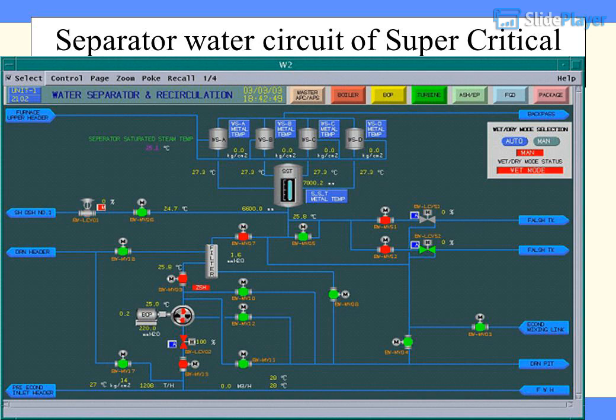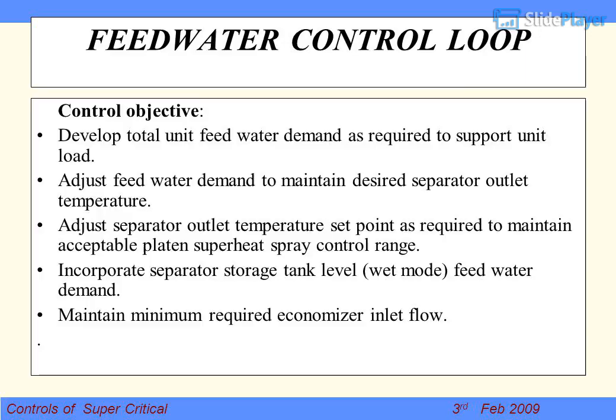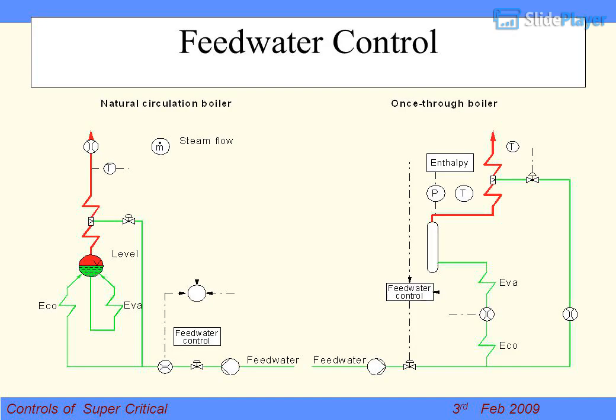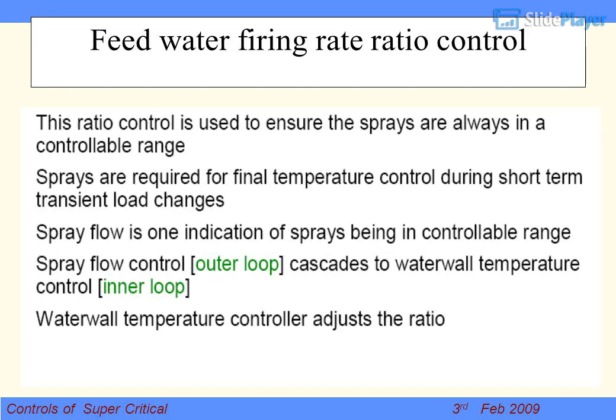Feed Water Control Loop — Control Objective: develop total unit feed water demand as required to support unit load. Adjust feed water demand to maintain desired separator outlet temperature. Adjust separator outlet temperature set point as required to maintain acceptable platen superheat spray control range. Incorporate separator storage tank level wet mode feed water demand and maintain minimum required economizer inlet flow. The most important control loop — there is no storage luxury. Feed water must respond per demand. This shows a comparison of how feed water is controlled in drum type versus once-through.